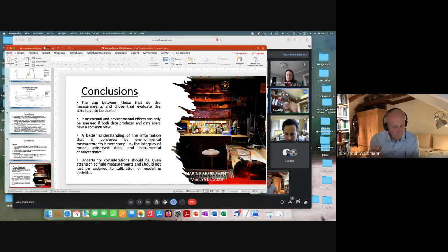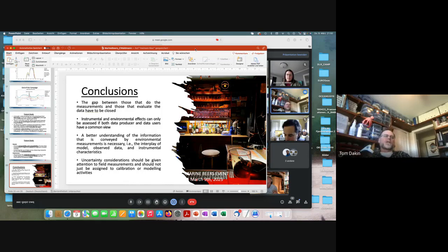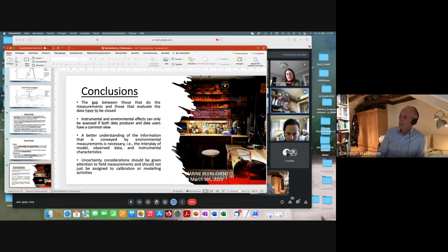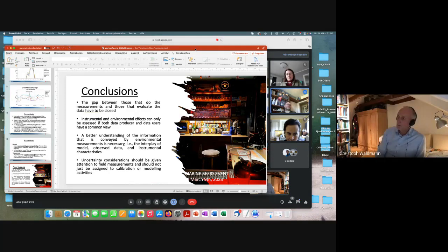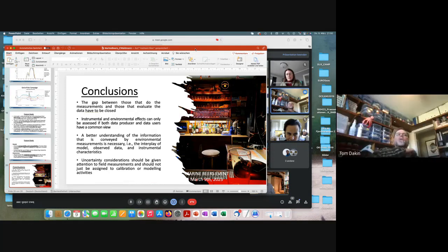I know, for example, the AML sensor is an electrode sensor. It's not inductive, but there is an external field on that, and it goes out a few centimeters away. Okay. So the Seabirds on the closed systems, where they're in the tubes with the ground electrodes on either end, you don't have to worry about those.